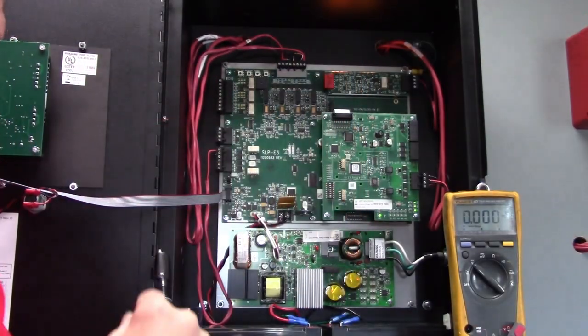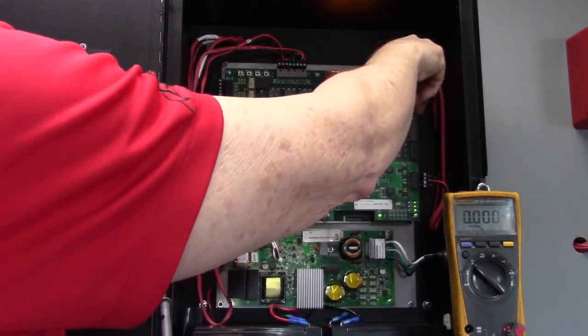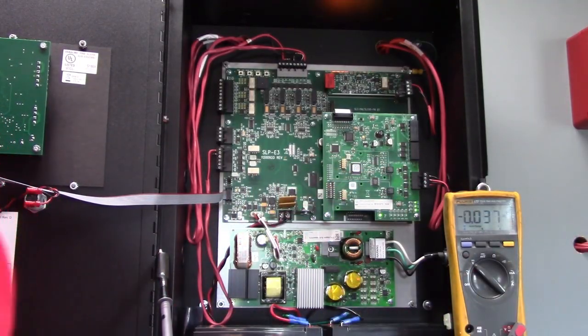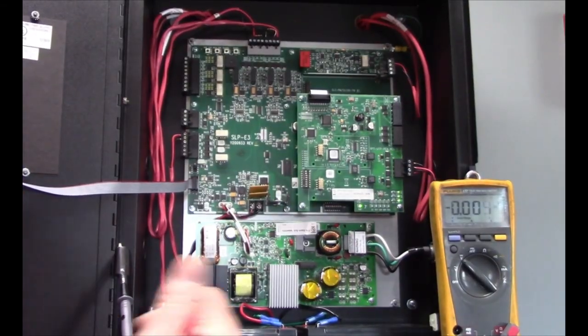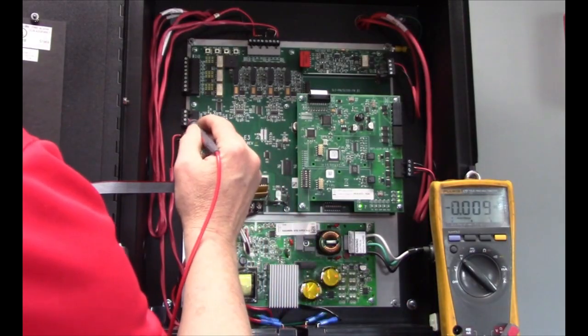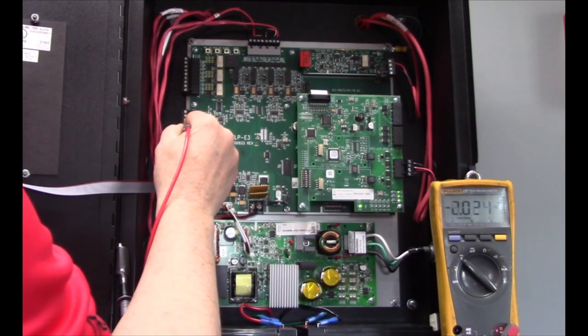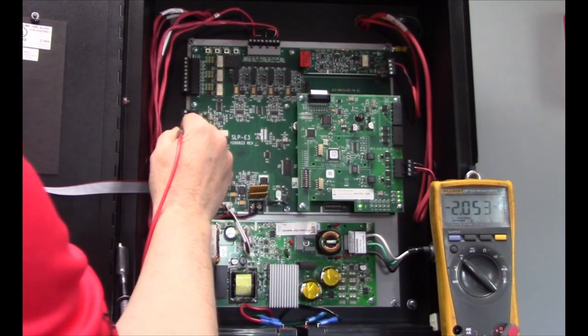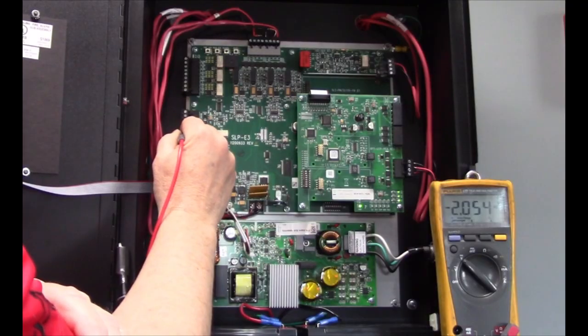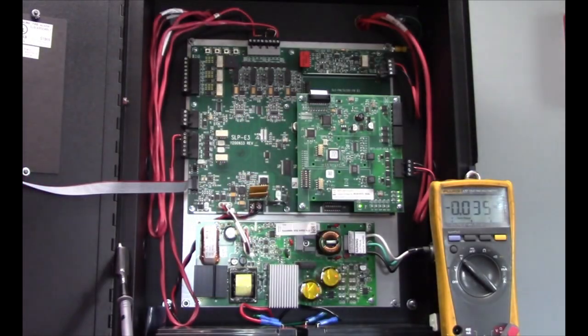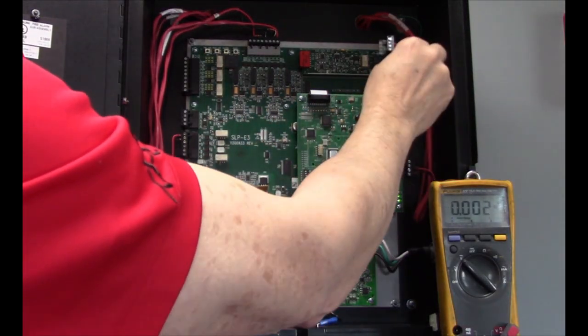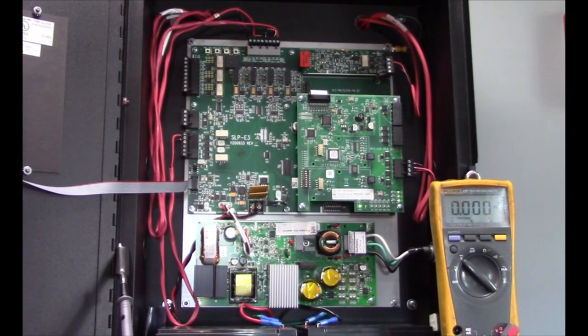And the only circuit left that's leaving the panel is our signaling line circuit. So let's pull that off. I'm going to get troubles because my devices are no longer communicating with the panel. I pulled the wires off. Now we can take our reading again. There we go. Now our negative reference is a 2 volt pulse. Notice it's pulsing to 2 volts and then about 0, back to 2 and 0. Our ground fault light up here went out. We're no longer in ground fault mode. So we know our ground fault is now on the SLC. So the next step will be to troubleshoot that.